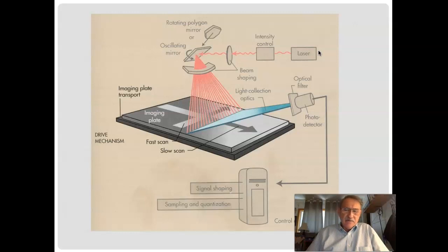I think that when we did imaging and technique, I gave you guys an example of a flashlight right at you, and so that shows up as a round circle. But if I turn it off this way, it becomes oval. If I turn it off this way, it becomes also an oval. So in order to keep it constant, we have these beam shaping optics, which, despite the fact that we're scanning the periphery or right in the center, we get the same signal geometrically with all of the values that it ought to, as opposed to having it distorted.